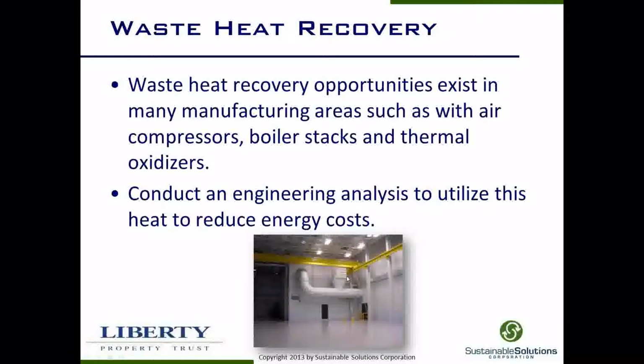You can see here we have some louvers on this ductwork, and notice the ductwork goes through the wall. We're actually feeding that waste heat into two or three other spaces in the building. By doing this, we're able to shut off the natural gas to heat this space by collecting the waste heat right off of the air compressors.